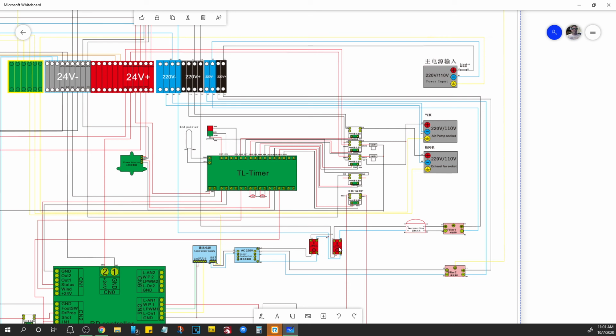And you can also do this diagnostics instead of looking for 110. It's a little more involved, but you can leave the system completely de-energized and do continuity checks here instead, and that's a lot safer. If you have a good understanding of how to work a meter, then I would suggest you try checking continuity at these places instead of checking for live power. But that's totally up to your skill and confidence level. If you have any worries about that, you may want to get someone in here to take a look that is familiar with electricity.